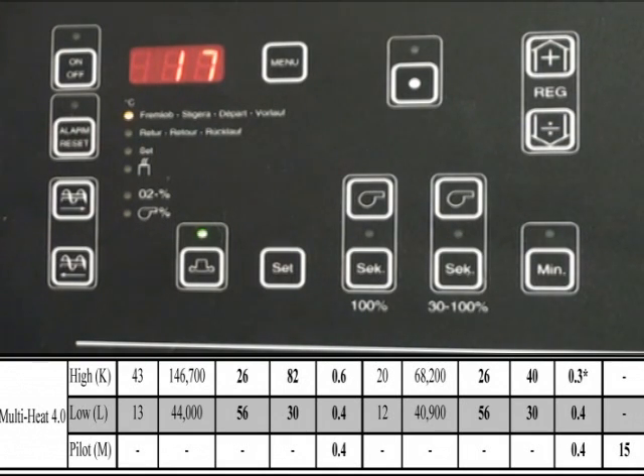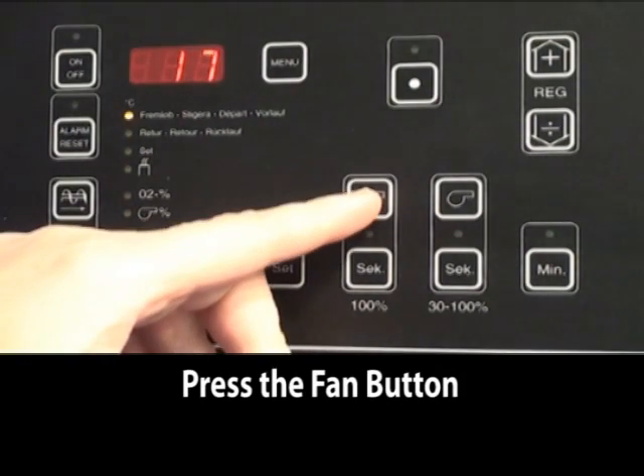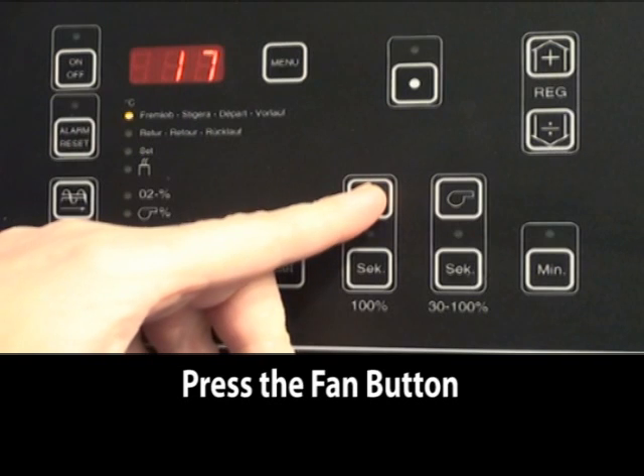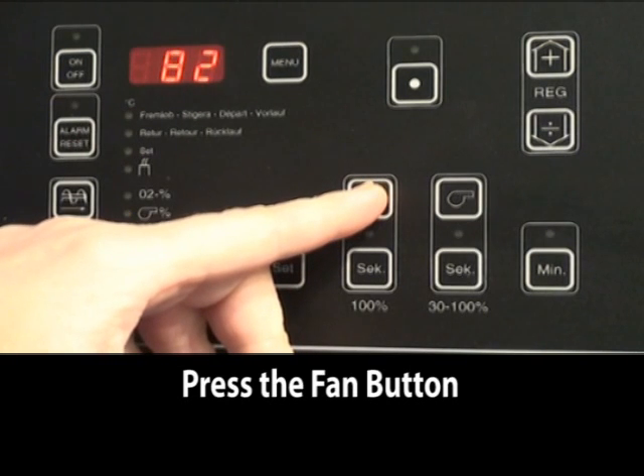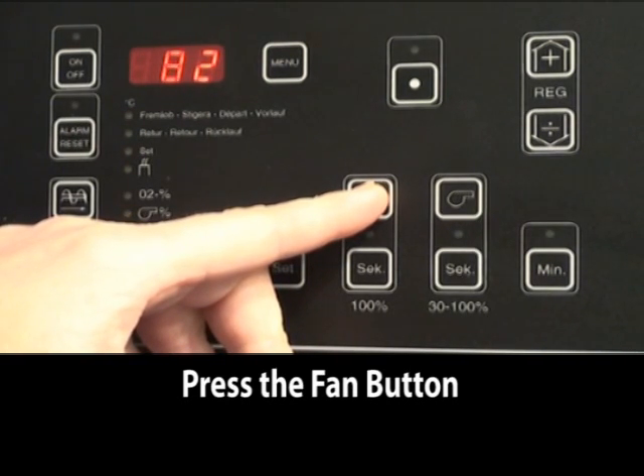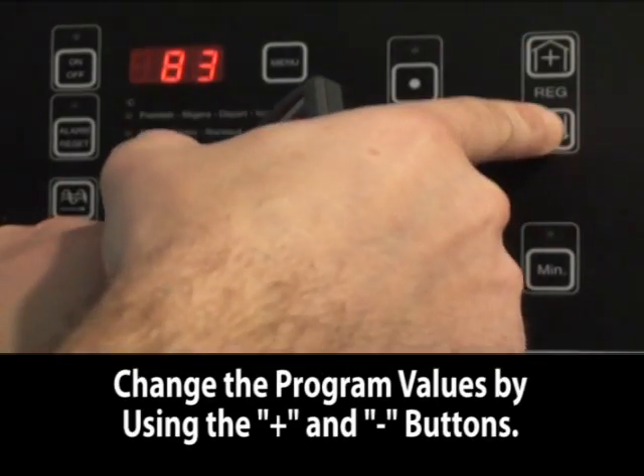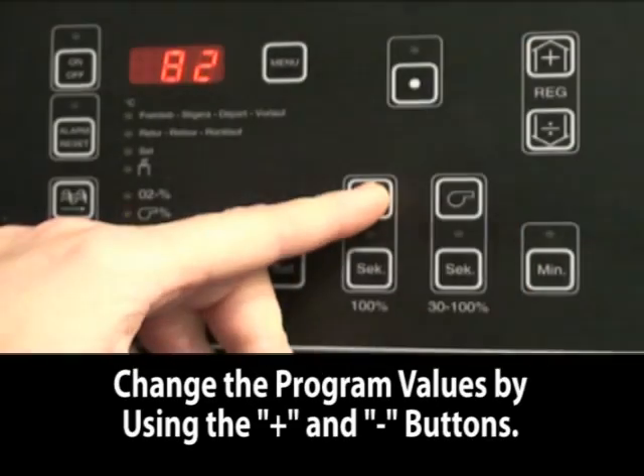First, we will do the air quantity at 100%. You hold down the blower button. It gives you a reading of 82%. That is correct, but if you needed to change, you can use the plus or minus button.